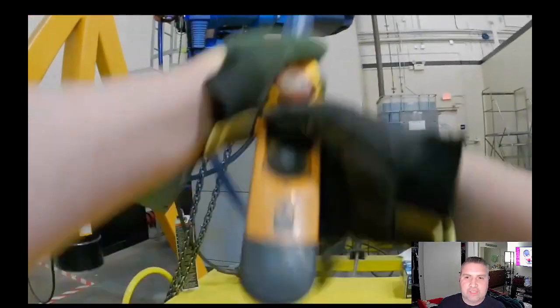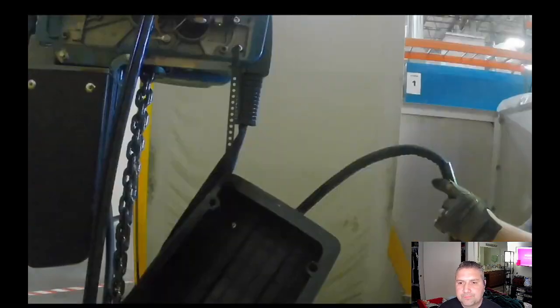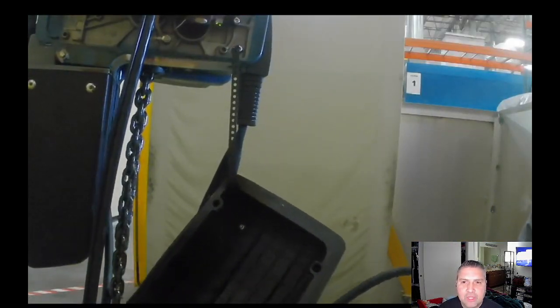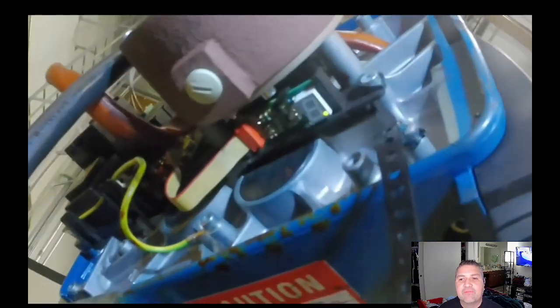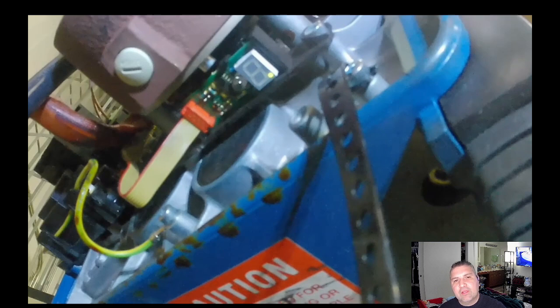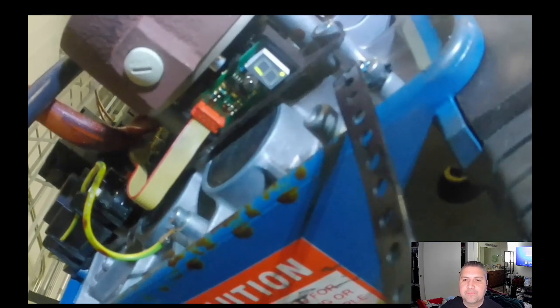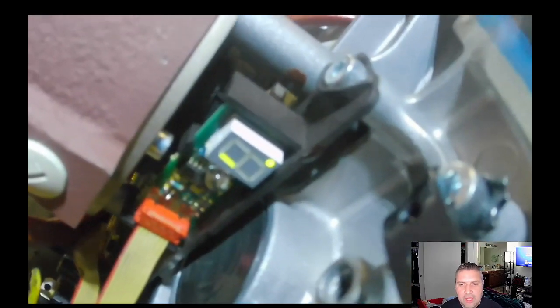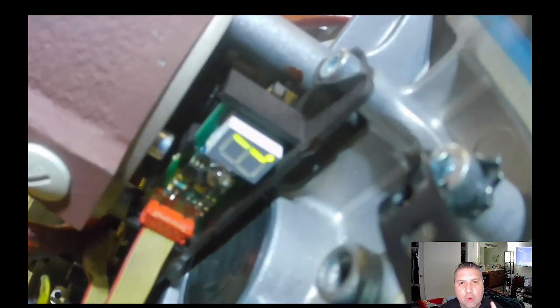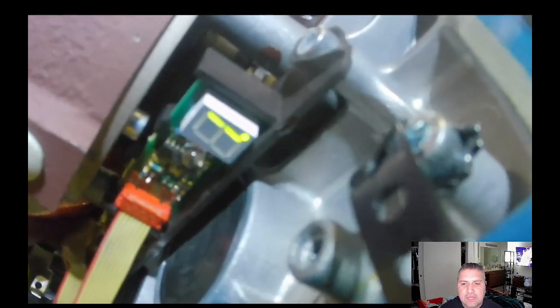Upon first startup, I noticed that the hoist would go down, but it would not retract. Every time I tried to go up, it wouldn't have any movement, but it gave a fault code. In these DEMAG hoists, it has an indicator module that will read out one letter or numeral at a time, and you can use that as the fault code indicator, almost like an HVAC system with the blinking lights. Every time I tried to go up, it gave me the fault code lightning bolt 1. So I had to look into what that was.